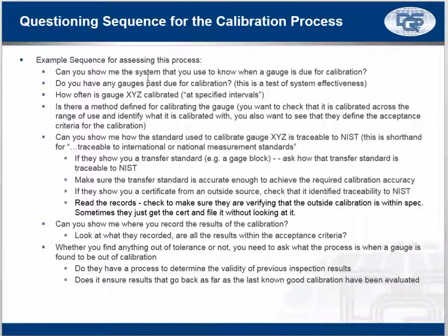When they show you that, ask: do you have any gauges that are past due for calibration? So if they have 100 gauges and they show you the system and 50 of them are past due, how do we feel about the effectiveness of the system? Not good. It could be a major nonconformance. That is why you're asking that question. Is this tracking system working? How often is gauge XYZ calibrated? They're supposed to be done at specified intervals. They need to define those intervals.